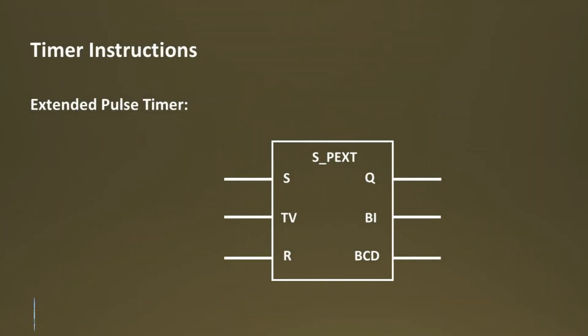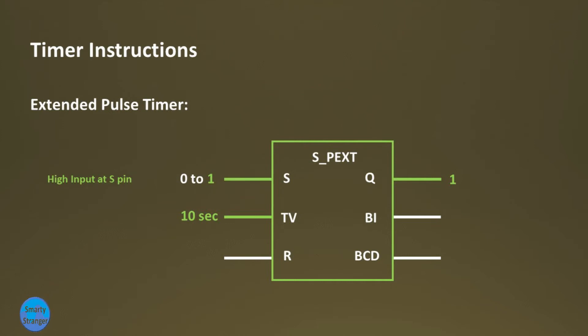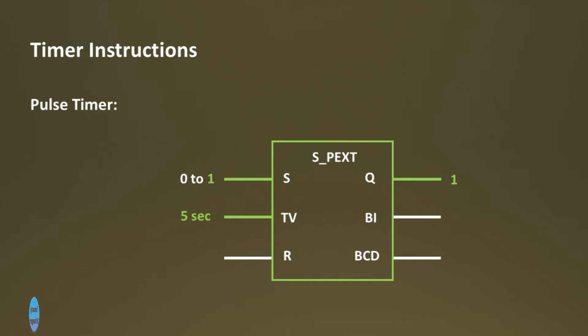Our second timer is the Extended Pulse timer, which is slightly different from the Pulse timer. When S input detects a change of signal from 0 to 1, the timer starts its timing and output Q is energized until time elapses. If the signal on S changes from 1 to 0 before time elapses, the timer does not stop until its timing is complete and output also remains 1. If S changes from 0 to 1 again before time elapses, the timer restarts its timing from the set value and output remains 1. If there is a high signal on R input while the timer is running, the timer and output stop immediately.